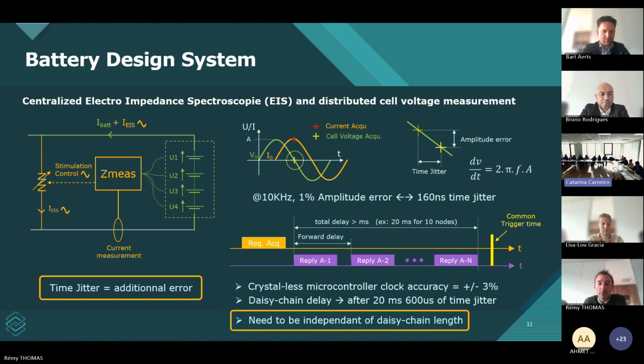Now, if we look at our battery system using a wireless optical daisy chain, it is necessary to trigger simultaneous measurement of cell voltage with delayed requests. As the BMS is located at the cell level, its manufacturing cost must be very low. For this reason, we have chosen to avoid using a crystal in the design. The clock accuracy is then around 3%. With this clock accuracy, a delay of 20 milliseconds will result in a time jitter of up to 600 microseconds, which is unacceptable for a centralized EIS implementation.